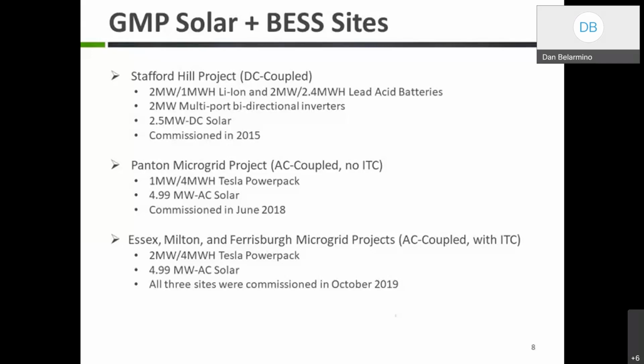As we learned after a few years of operating Stafford Hill, and as battery manufacturers improved with lithium-ion becoming a better technology, we realized that an AC coupled system is much better based on our needs today and the markets we participate in. The main disadvantage we learned from the DC coupled system is its curtailed or limited performance during peak reduction or time spent in the regulation market, which my next slides will show, comparing operation between DC coupled and AC coupled systems.